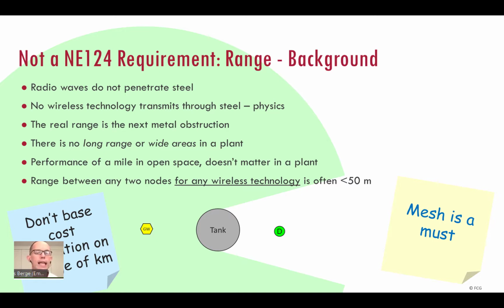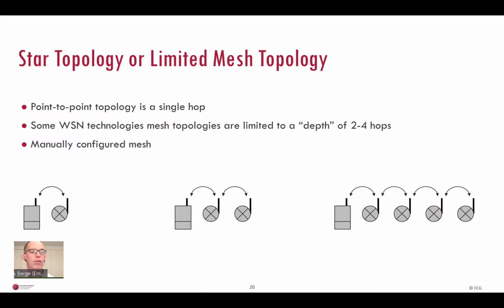Okay, next, range. The most interesting fact is that NE124, the NAMUR standard or NAMUR recommendation, does not specify range from sensor to gateway as a requirement because it doesn't make sense in a plant full of steel. Since radio does not penetrate steel, there is no long range or wide areas in a plant. No wireless technology transmits through steel. It's physics. Therefore, the real range of wireless in a plant is only as far as the next metal obstruction. Range of a mile or more in open space has no meaning in a plant. So don't design your wireless sensor networking thinking a star topology with a 1 kilometer range will cover the whole plant. It won't.